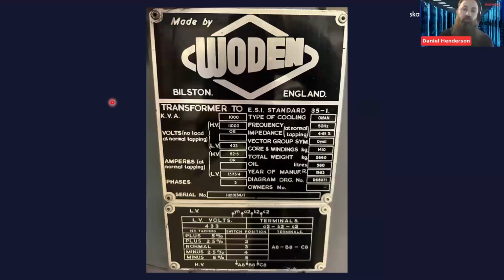Just to give you a visual representation of that, this is a transformer rating plate. When we're talking about the rating, this is the typical rating of a standard transformer, measured in kVA, so a 1000 kVA or 1 MVA transformer. What Steve's saying there is that if we have a standard linear load, none of those sources that we previously discussed, then we'd look to load that up to ideally around 80% to give us that bit of headroom. We would load that to 800 kVA and give us that 200 kVA buffer.